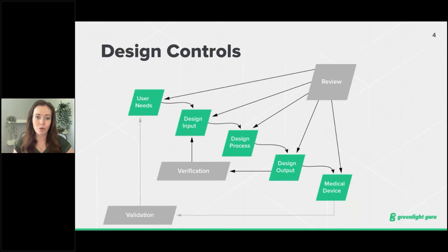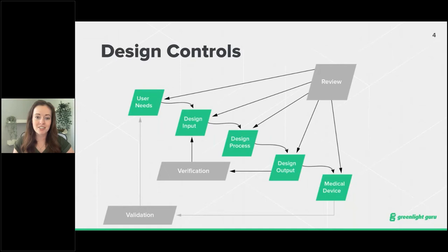Design controls help increase the likelihood that design transfer to production will result in a device appropriate for its intended use. In practice, they provide manufacturers and designers with improved visibility of the design process. From personal experience, having a robust design control process is a night-and-day difference from a lacking design process, and it will ultimately help save time and money. Designers benefit from an enhanced understanding of the degree of conformance to user and patient needs, and it also improves communication and coordination among all participants in the process.